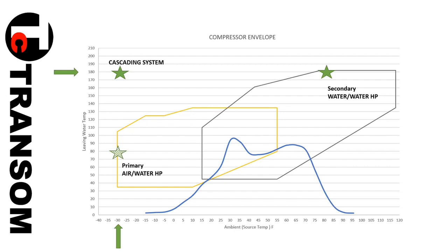Is that would be running two compressors at that COP though, right? You would? Yeah, no, basically the THR you generate here becomes the source temperature for this one, so you don't get anything for it, right? So all you can do is figure out how much total heat of rejection you get out of the second stage. And then I took in the wattage from this compressor and this compressor and put them together. And that's when we got those higher numbers.